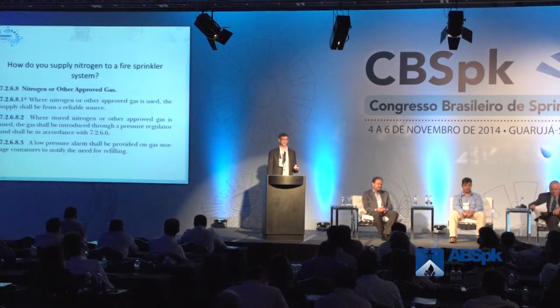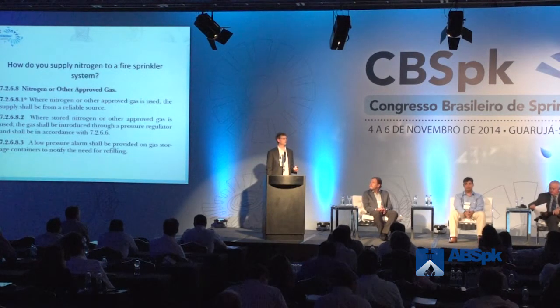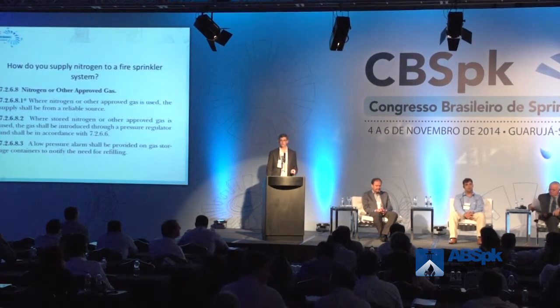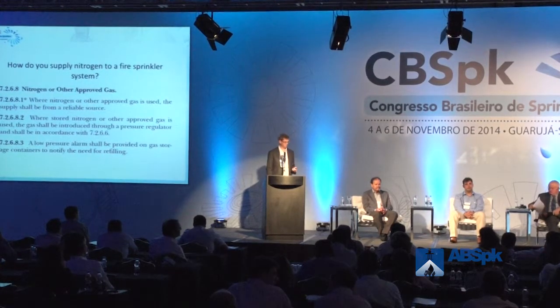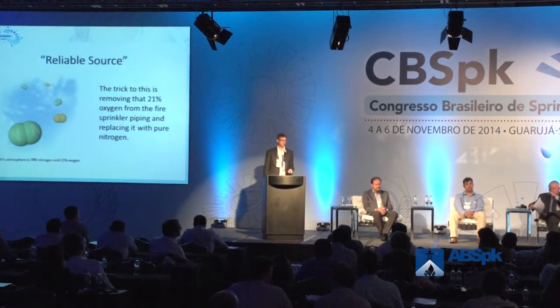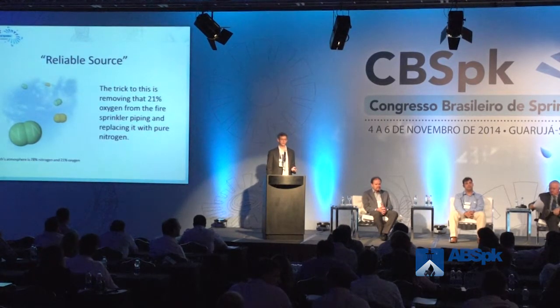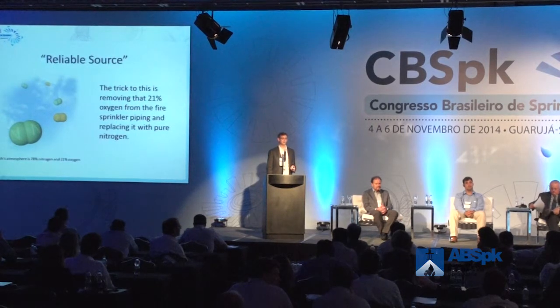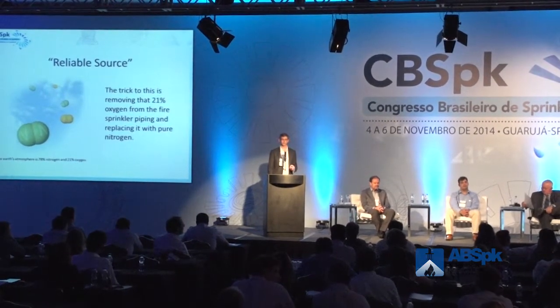So how do you supply nitrogen to a fire protection system? That's the question. We used to use cylinders to fill the sprinkler system up with nitrogen. The only issue with that is there's a lot of maintenance involved in replacing and changing out cylinders, which has caused problems in the past. A new, more reliable source is actually the atmosphere. The atmosphere is 78% nitrogen, 21% oxygen. The trick is you have to remove that oxygen to get a high percent of nitrogen. So how do you do it? Well, you can actually remove the oxygen from the air.